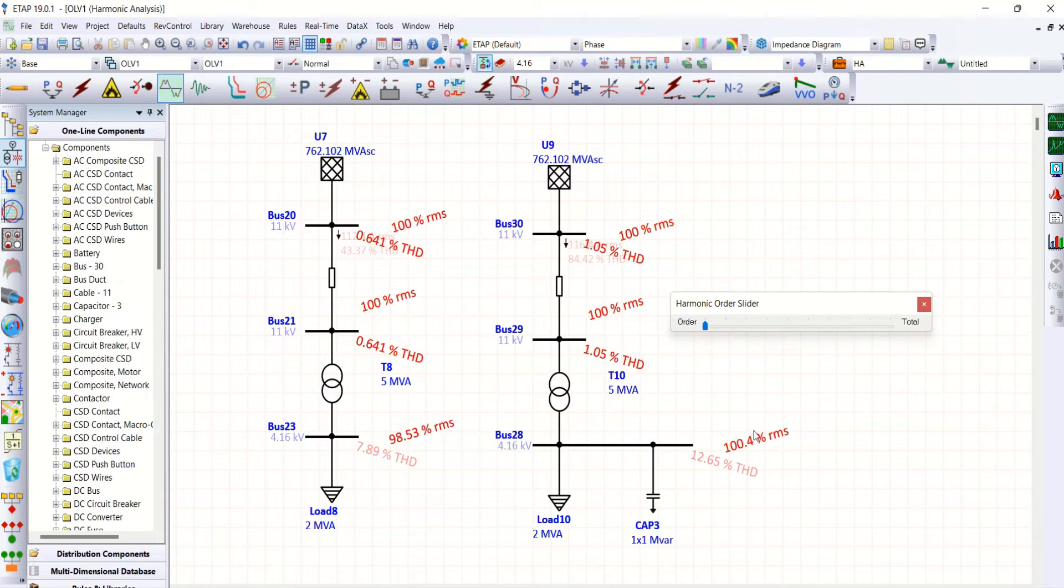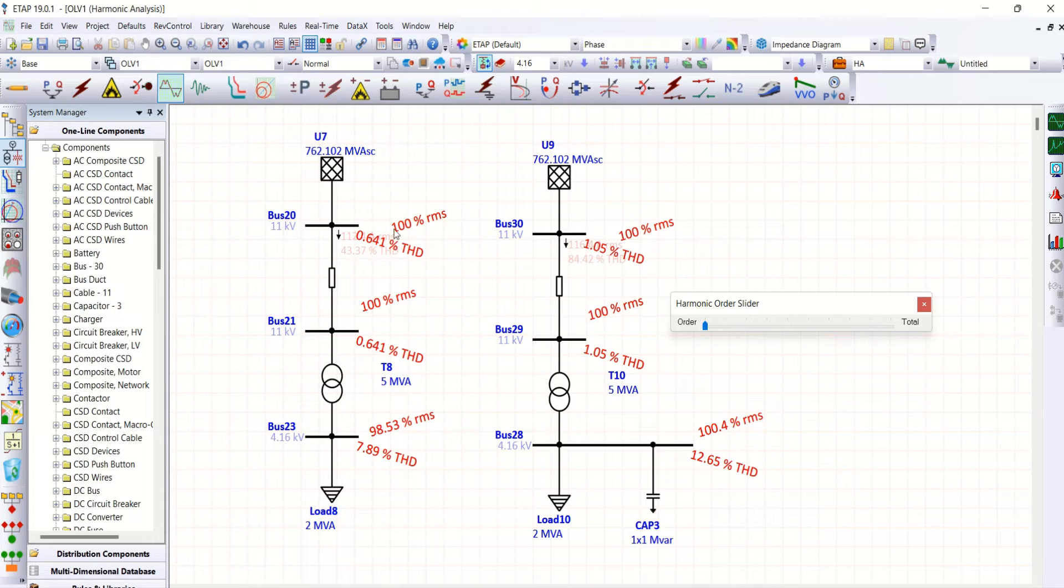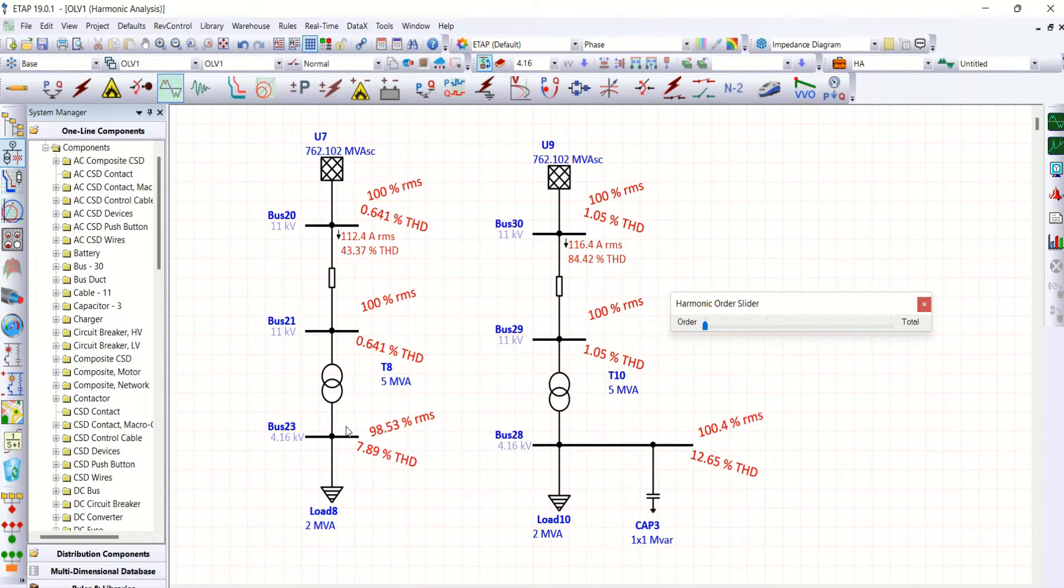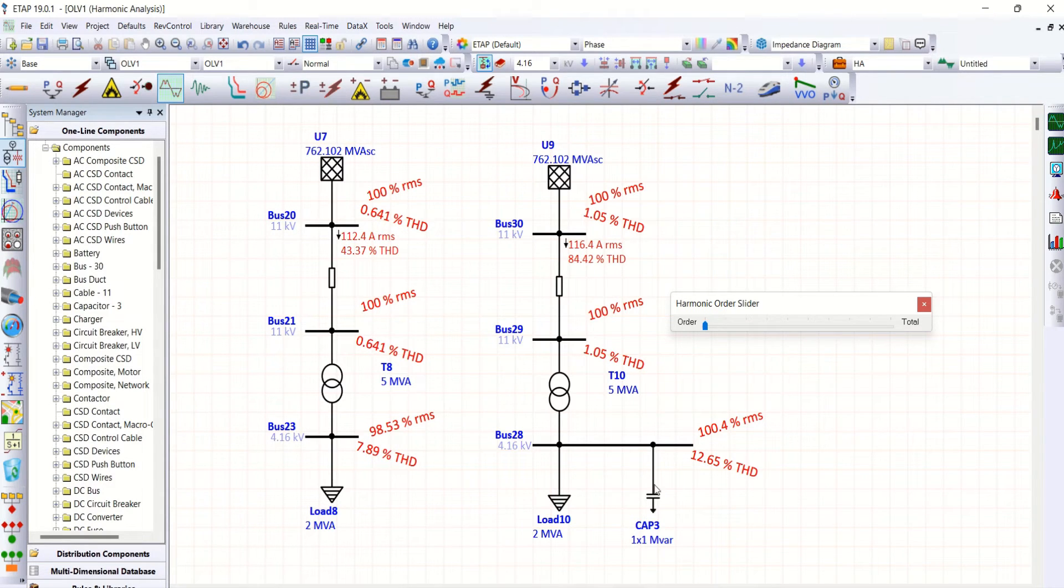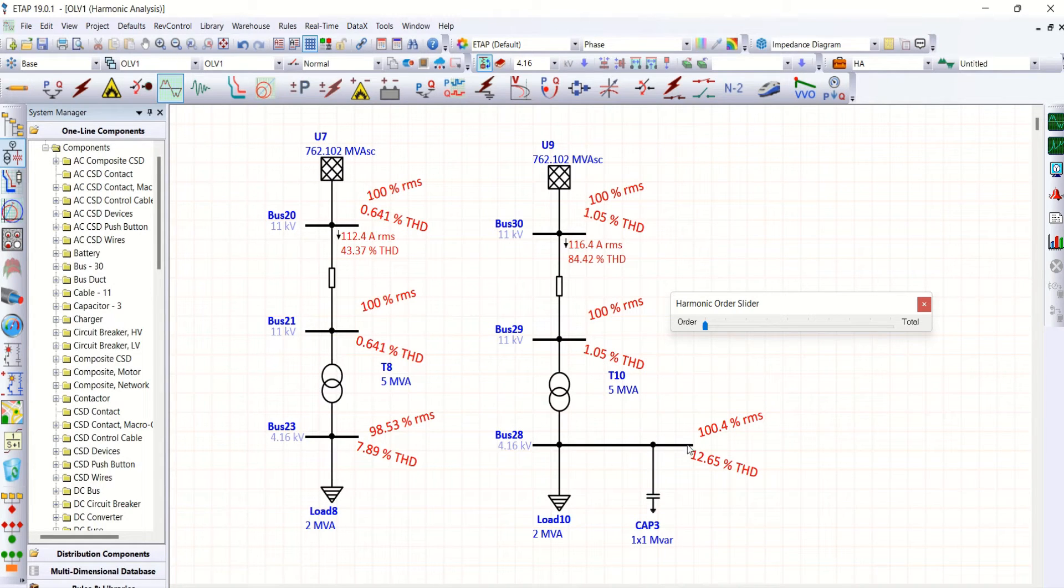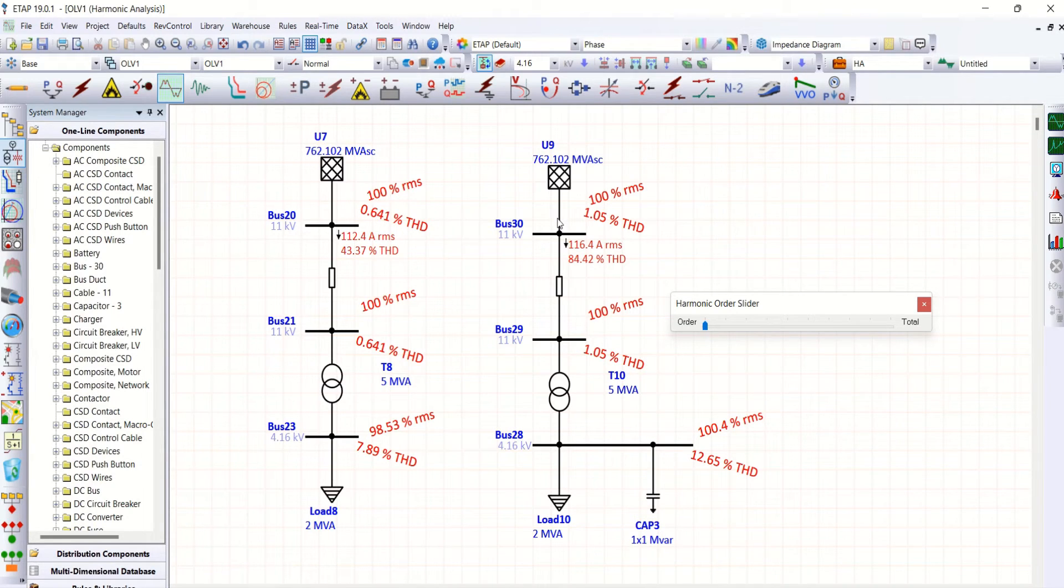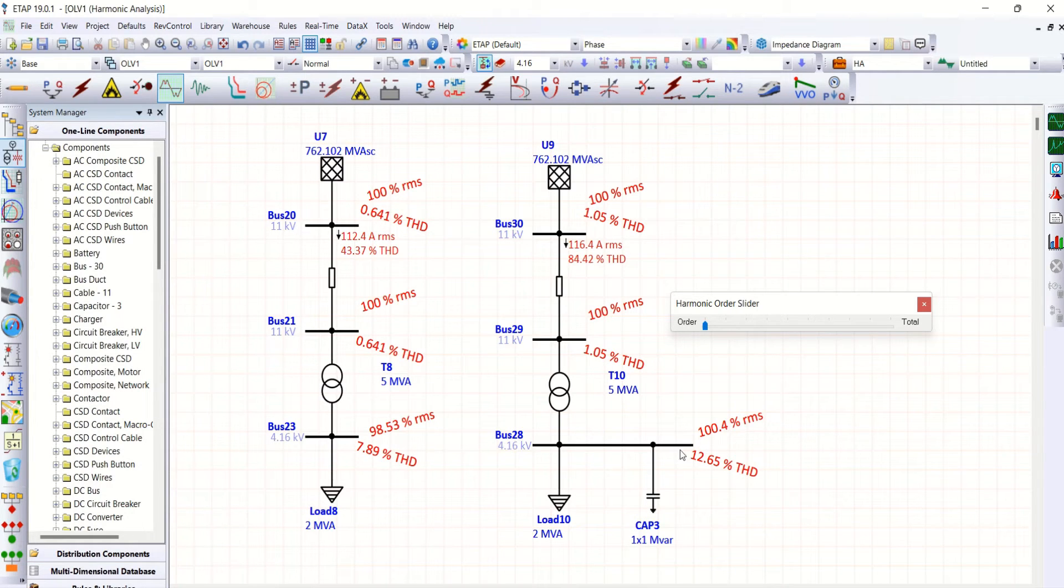See the total harmonic distortion on both the circuits. Here the circuit or system without capacitor bank has 7.89% of THD, whereas on the same bus with capacitor bank we have 12.65% of THD. That means capacitor bank connection not only improves the power factor but also increases total harmonic distortion.